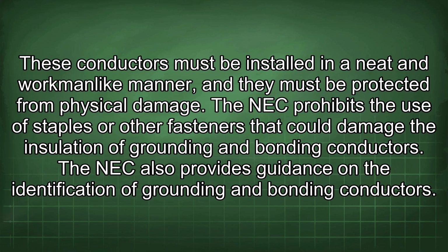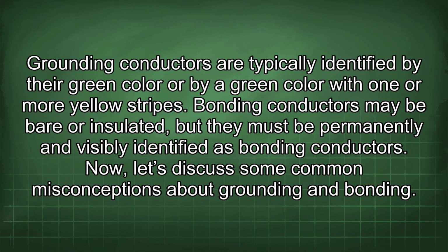The NEC also provides guidance on the identification of grounding and bonding conductors. Grounding conductors are typically identified by the green color or by a green color with one or more yellow stripes. Bonding conductors may be bare or insulated, but they must be permanently and visibly identified as bonding conductors.